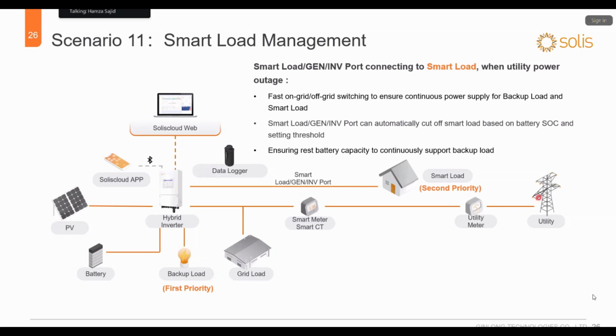So what will be the working logic? Let's suppose the grid outage happened and the PV is also not sufficient for the support, like suppose it is night time. Both backups are running out. Okay. Now the battery is discharged to a certain limit, whatever you fix. Like you can fix the SOC from 100% to 20% where you want to close this second smart port load.